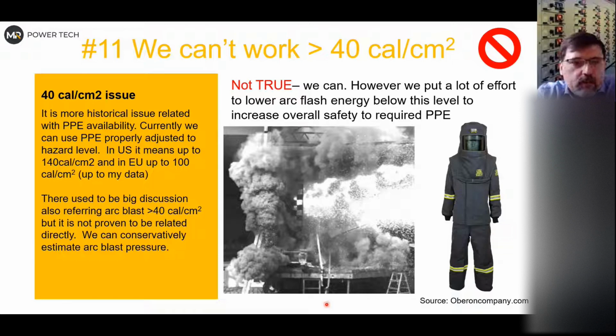So as far as I know, arc blast pressure is not, from my perspective, I haven't seen any case proven that arc blast killed someone. On the other hand, it's quite hard to protect yourself against arc blast. So technically it's not true. We can work above 40 calories if it's needed, because we have PPE up to 140. And there are locations sometimes where you might need such PPE to just do something, like an electrical furnace or in glassworks.